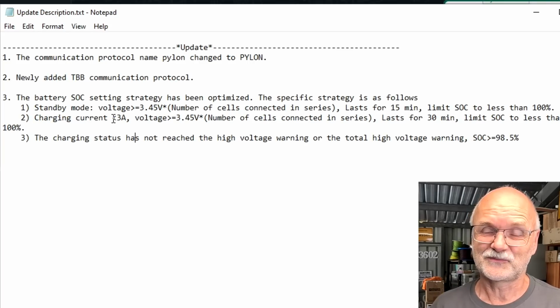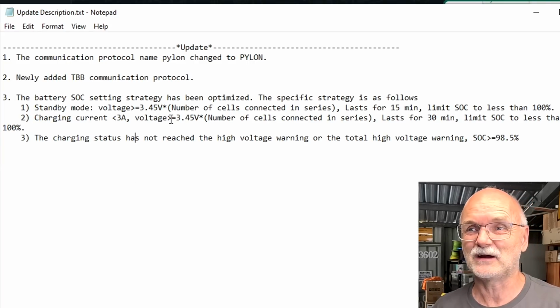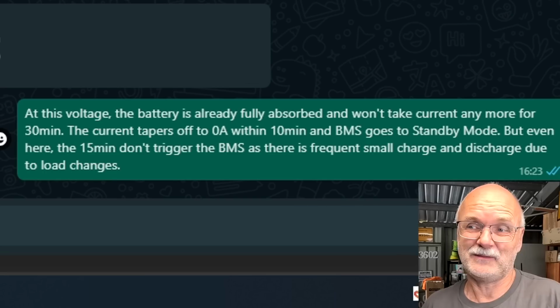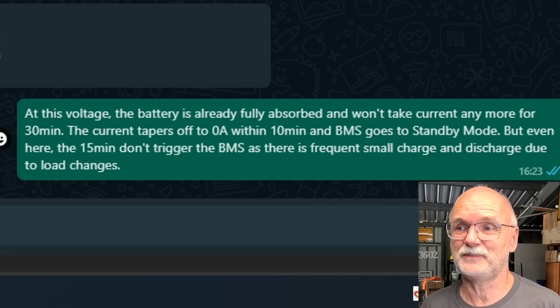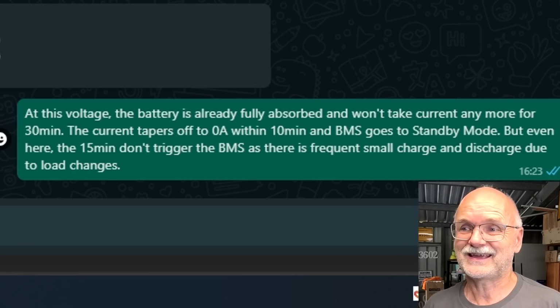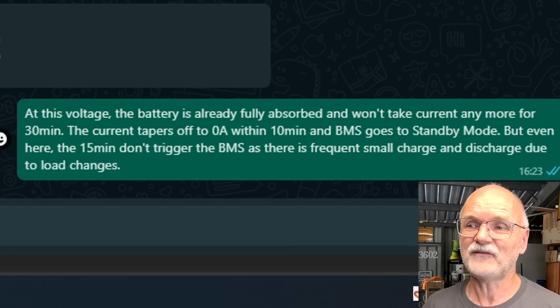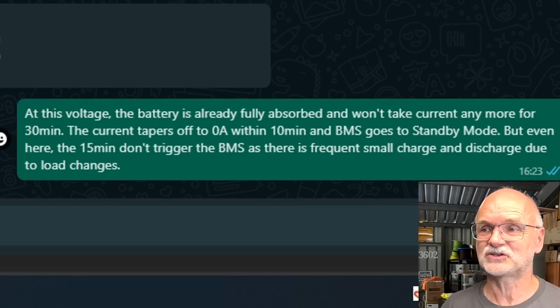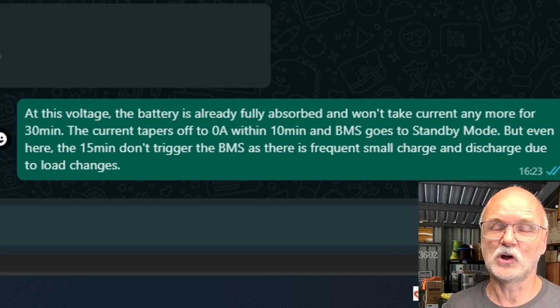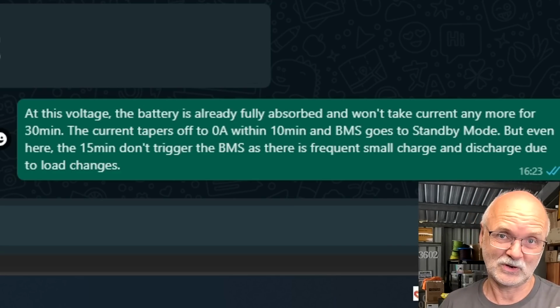Charge current smaller than 3 amps, voltage higher than 3.45 volts, lasting for 30 minutes. Back then I told them at this voltage the battery is already fully absorbed and won't take current anymore. The current tapers off to 0 within 10 minutes and then the BMS goes to standby mode. But even here the 15 minutes don't trigger the BMS, as there is frequent small charge and discharge due to load changes, as I just explained.